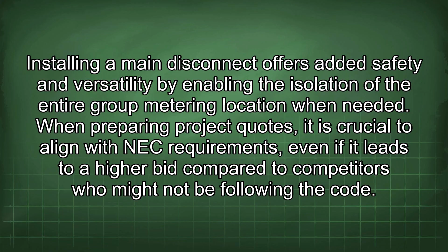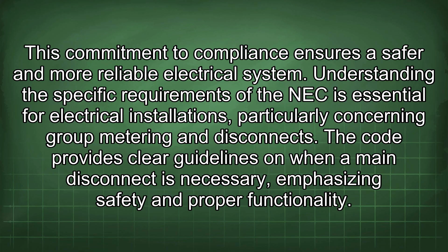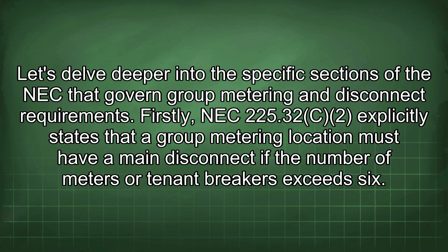Understanding the specific requirements of the NEC is essential for electrical installations, particularly concerning group metering and disconnects. The code provides clear guidelines on when a main disconnect is necessary, emphasizing safety and proper functionality. Let's delve deeper into the specific sections of the NEC that govern group metering and disconnect requirements. Firstly, NEC 225.32C2 explicitly states that a group metering location must have a main disconnect if the number of meters or tenant breakers exceeds 6. This rule is designed to provide a means of disconnecting all power to the group metering installation in case of an emergency or for maintenance purposes.